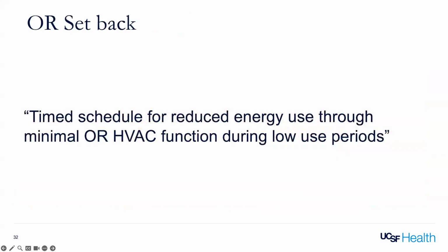This brings us to the concept of OR setback. OR setback refers to a time schedule for reduced energy use through minimal OR HVAC function during low-use periods in an operating room. These reductions can be set to a specific schedule or timer, can be unique to each operating room within a hospital, and can be manually overwritten when necessary.